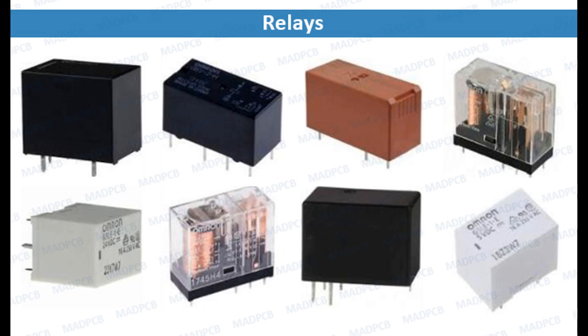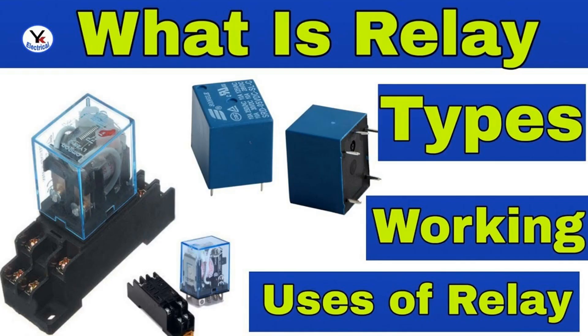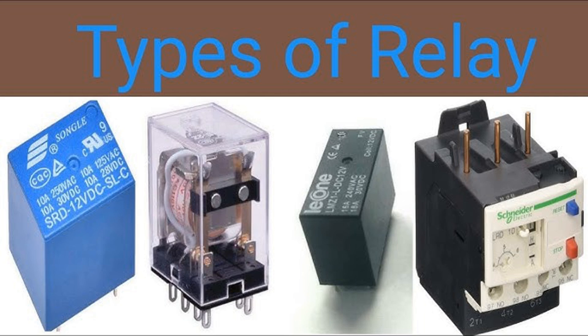Working Principle: Normal Operation — under regular conditions, the current flowing through the relay is within the acceptable range, and the relay remains inactive. Fault Condition — when a fault occurs, like a short circuit or overload, the current exceeds the relay's preset threshold. Relay Activation — the current sensing element detects this excess current, and the operating coil produces a magnetic force proportional to the current. Once the current exceeds the set threshold, the magnetic force moves the relay contacts. Tripping Signal — the relay sends a signal to the circuit breaker to trip, disconnecting the faulty section and isolating the fault to prevent further damage.